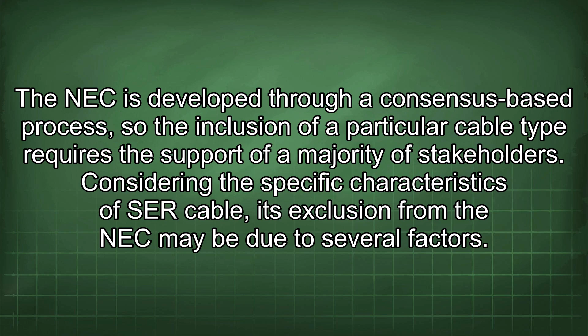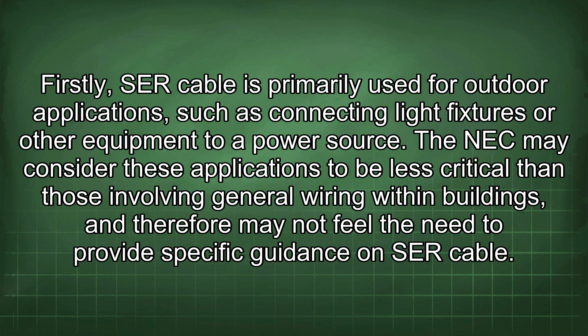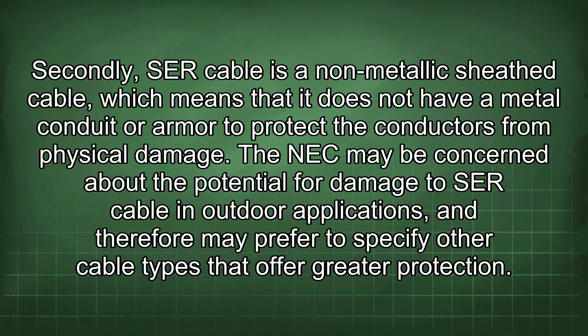Firstly, SER cable is primarily used for outdoor applications such as connecting light fixtures or other equipment to a power source. The NEC may consider these applications to be less critical than those involving general wiring within buildings, and therefore may not feel the need to provide specific guidance on SER cable. Secondly, SER cable is a non-metallic sheathed cable, which means that it does not have a metal conduit or armor to protect the conductors from physical damage. The NEC may be concerned about the potential for damage to SER cable in outdoor applications, and therefore may prefer to specify other cable types that offer greater protection.